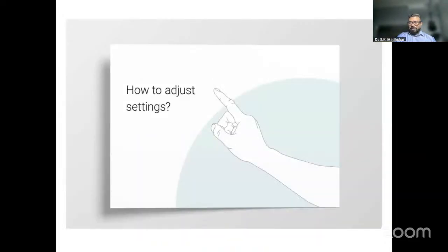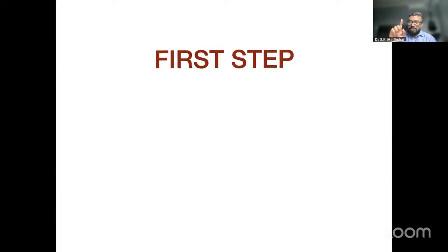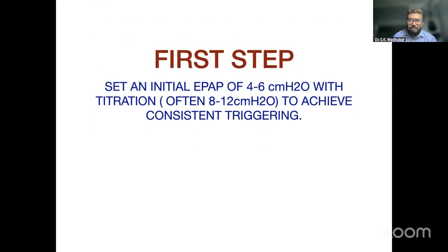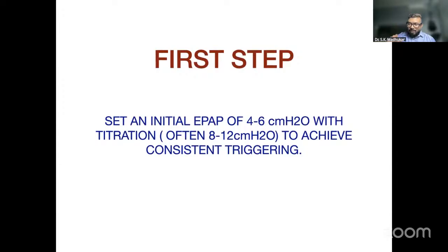Once you have done it, now your ventilator is on, the interface is on the patient's face, and the interface is connected with the ventilator with the tube. How are you going to adjust the settings? What are you going to do now? So the first step is set EPAP. The first task is set EPAP, not IPAP. The initial EPAP should be 4 to 6 centimeter H2O. I keep it around 5.